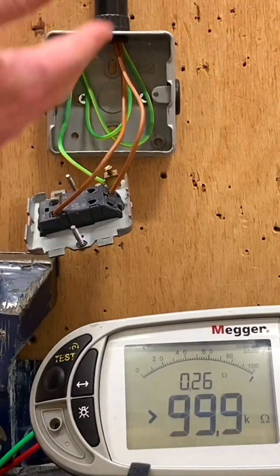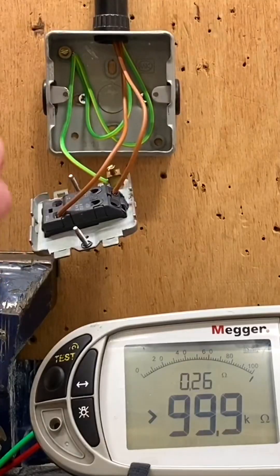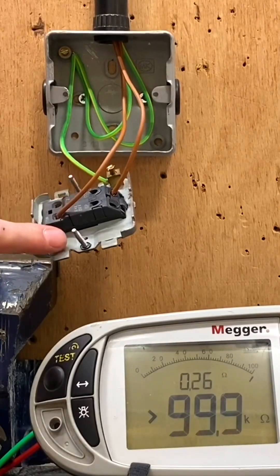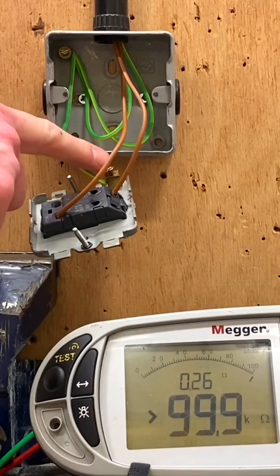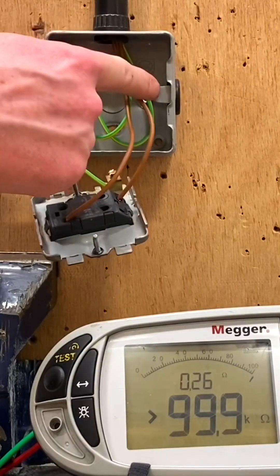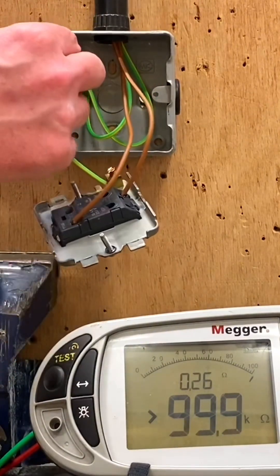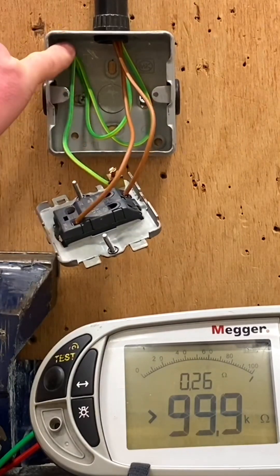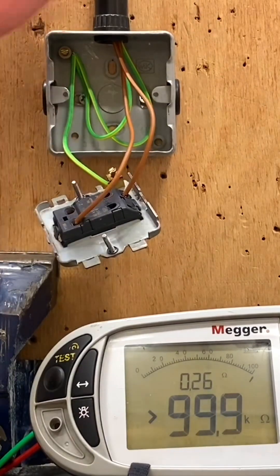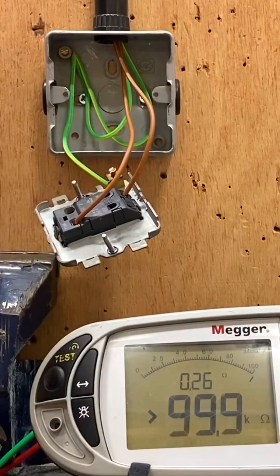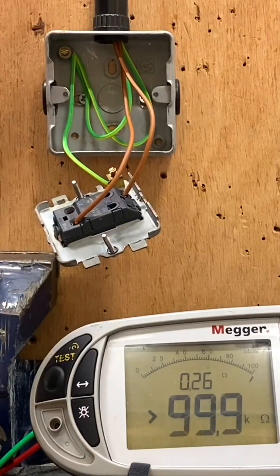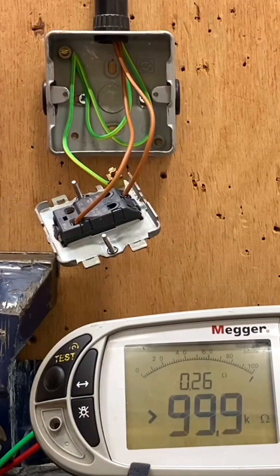This proves the CPC got to the front plate, got to here, got to here, and got to the box as well. It's really important the frame is earthed and the box is earthed, and we don't just prove it on the actual CPC terminals. We're now going to go up to the light, operate the switch when we're up there as part of the polarity test, and prove there is a CPC connected to the light.